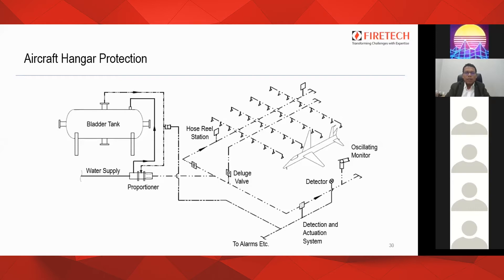Whenever a foam system is provided for an aircraft hangar, it can be either overhead sprinklers with a low expansion foam system — that is option one — or the second option is a high expansion foam system.